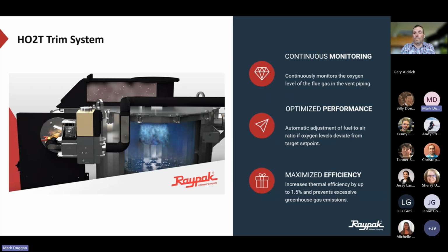So this is really nice for places like Colorado, where you get those huge swings in pressures and air temperatures. Say the boiler started up in September. Now it's February, that air pressure's dropped. There might be a little less oxygen in the air. So being able to adjust that firing or adjust those air shutters and the oxygen levels automatically, without having to send a guy to a job site to do another startup in the winter versus the fall, versus the spring, is really nice.